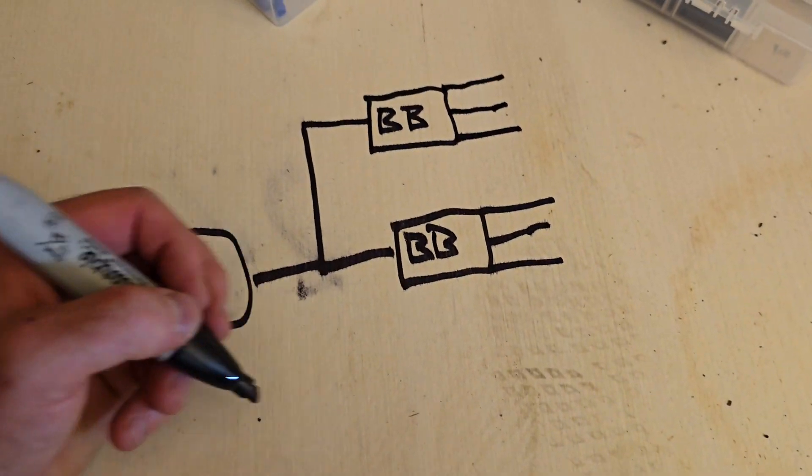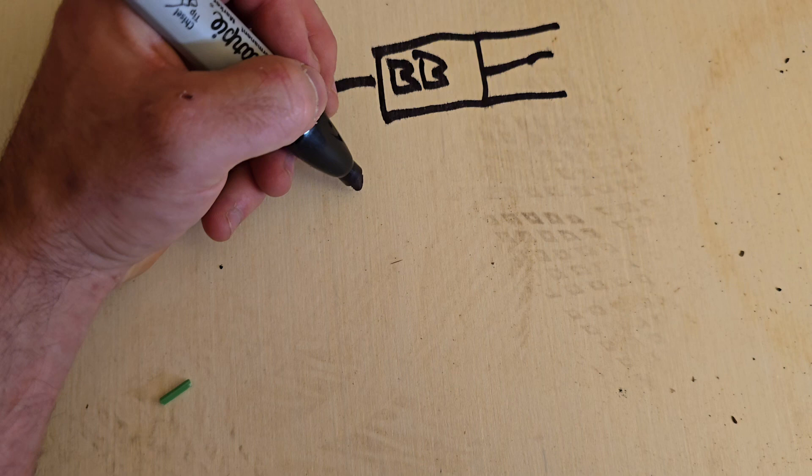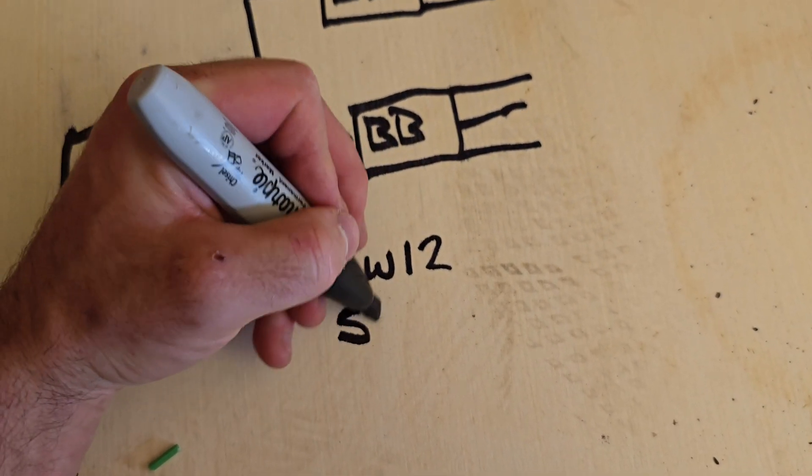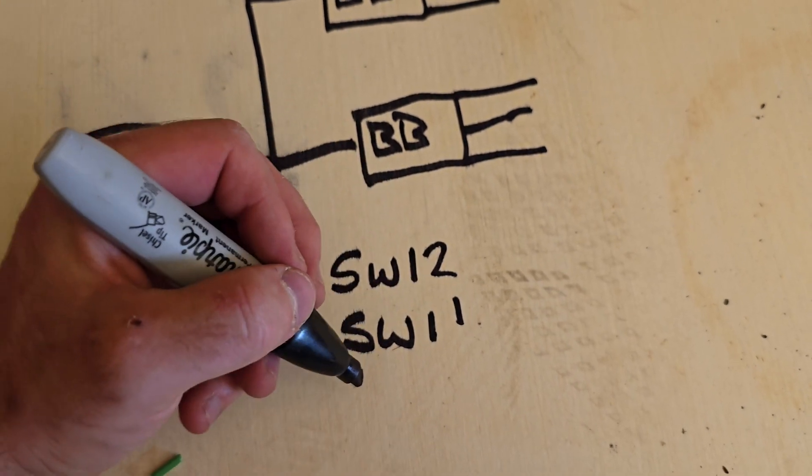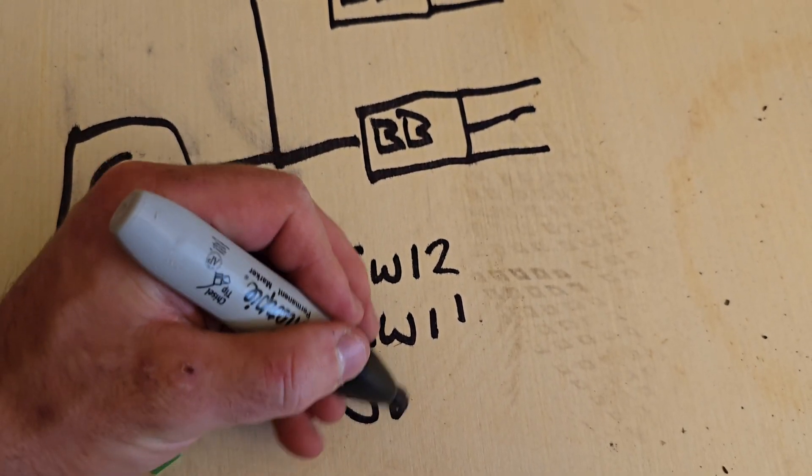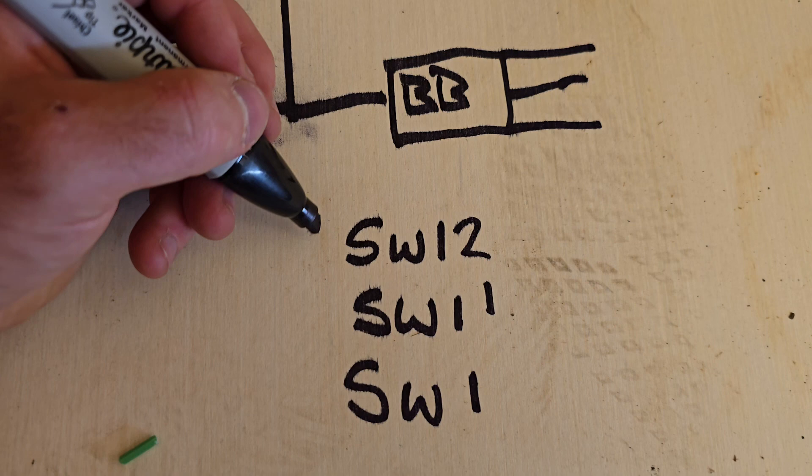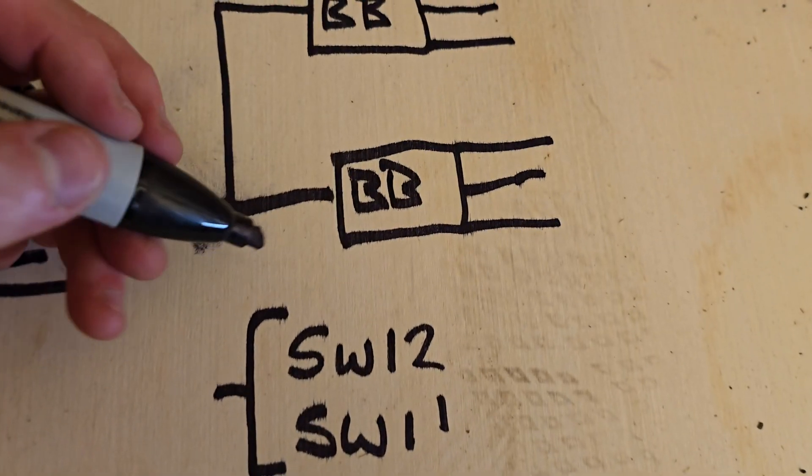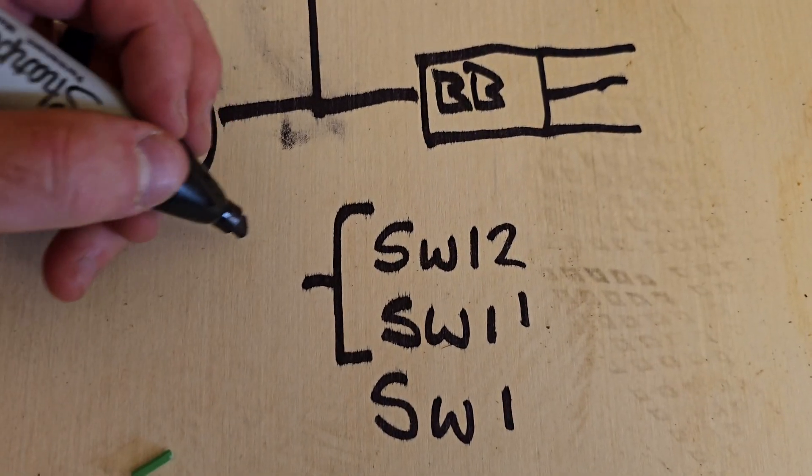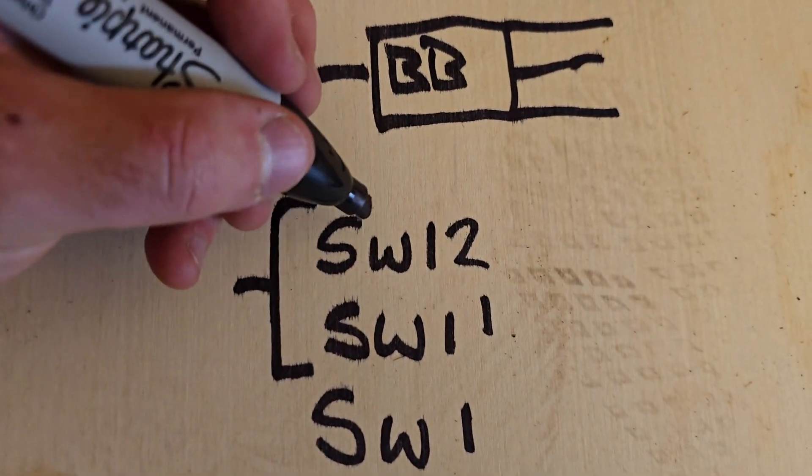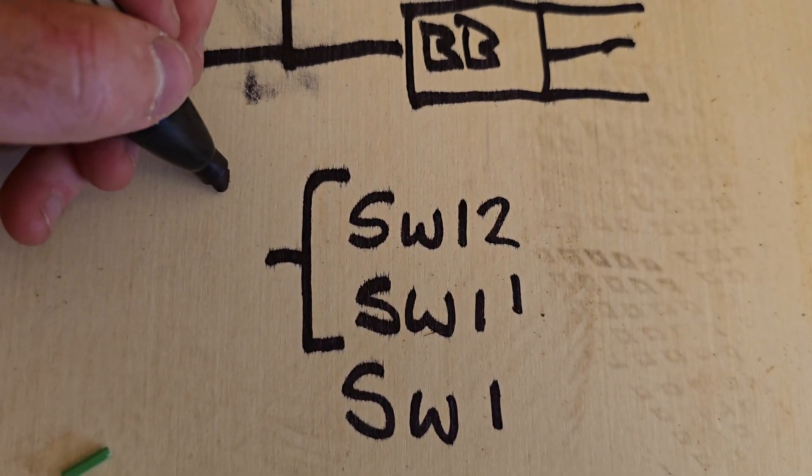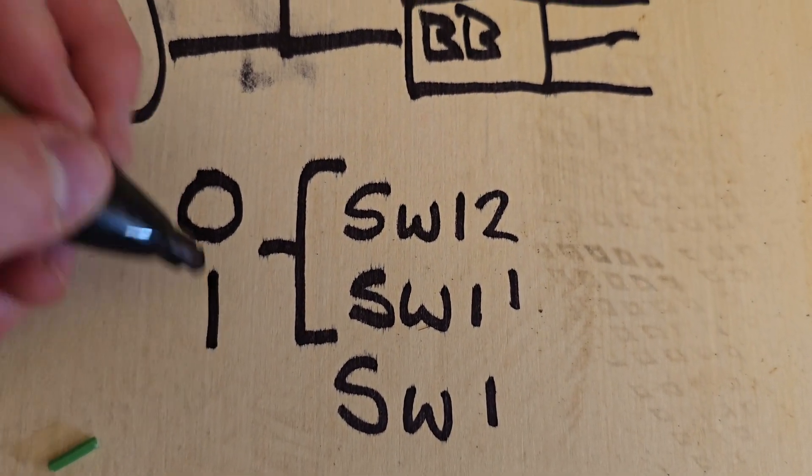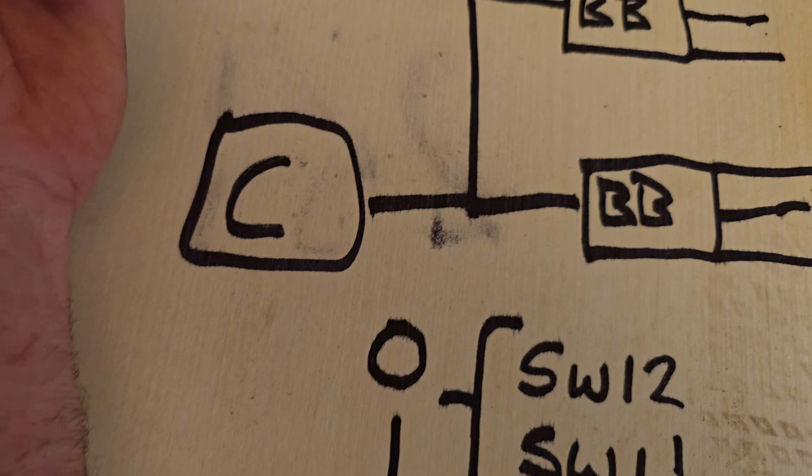Now for the DIP switches, you're going to be looking on these branch boxes specifically for SW12, SW11, and SW1. The first two are to address the actual branch box itself. We're going to start at 01. SW12 is your tens digit, so that won't be set. SW11 is your ones digit, so we're going to set that to one. That's telling your outdoor unit that this branch box is now called 01.